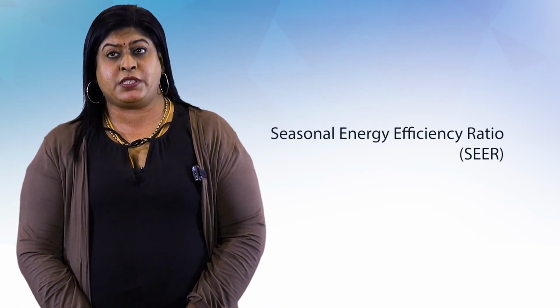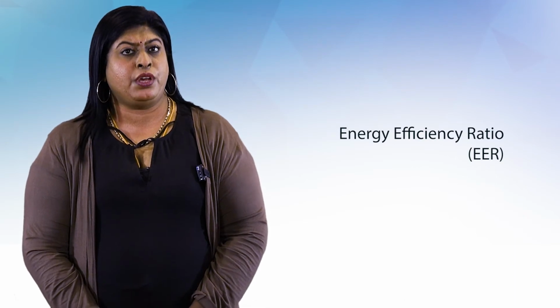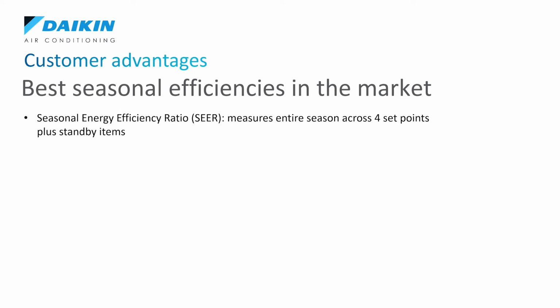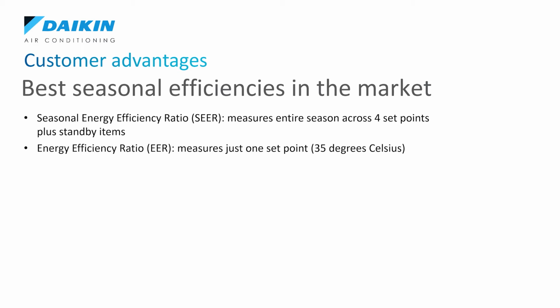Now let's talk a bit more on seasonal efficiency, as I want to stress the difference between seasonal energy efficiency ratio, known as SEER, and energy efficiency ratio, known as EER. SEER measures how efficiently an air conditioner operates over an entire season by measuring across 4 set points: 35, 30, 25, and 20 degrees Celsius, and includes power consumption of standby items such as PCBs. EER measures efficiency at a single operating temperature, 35 degrees dry bulb. Now 35 degrees is a lot, really a lot.